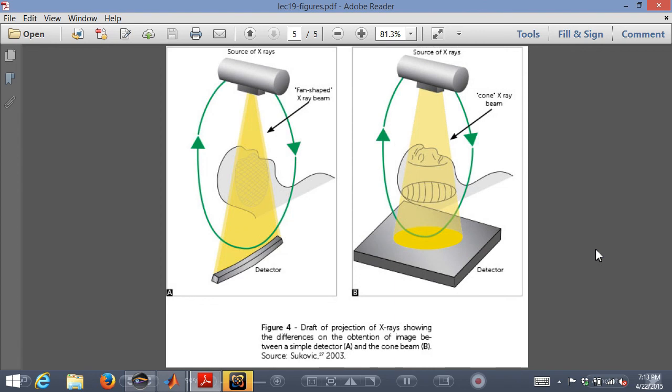And then even more modern is something called cone beam CT. Instead of getting one slice through the patient, as in a fan beam geometry, you have an aperture that lets a cone of angles through the patient. And instead of a one-dimensional detector, you have a two-dimensional detector. So at every angle, you get an image that is like a projection, and then I need to reconstruct the 3D geometry of the patient from a whole bunch of these images. As you can imagine, the mathematics for that is even worse than what you just saw here, but the fundamental ideas apply. I think you would call this a generation 7 CAT scanner, probably a cone beam. And certainly a lot of my colleagues in medical physics are using cone beam CTs in their research.